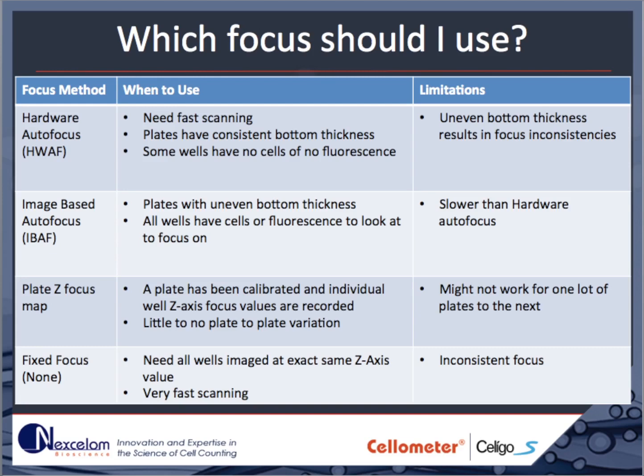It is important to know when each focusing method can be used. Hardware-based autofocus requires high-quality plates, such as those listed as recommended on the Nexcelom website. It is used in workflows where there are very few cells in each well, such as when verifying the deposition of one cell per well. Hardware-based autofocus can fail on plates with inconsistent plastic thickness. Image-based autofocus works well in both high- and lower-quality plates, as long as there is enough contrast in each well. It is recommended that there be at least 1,000 cells in each 96-well to use image-based autofocus.